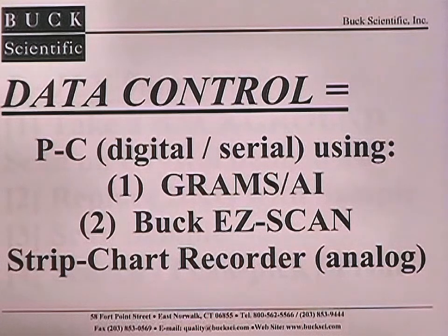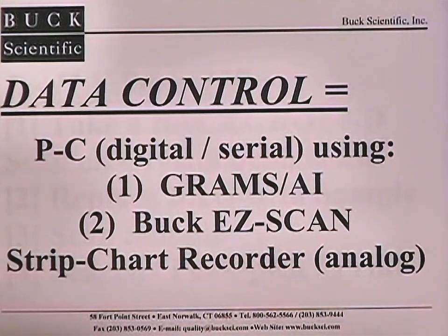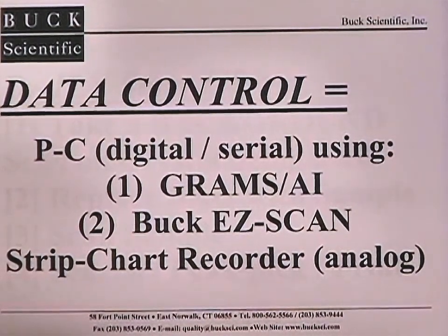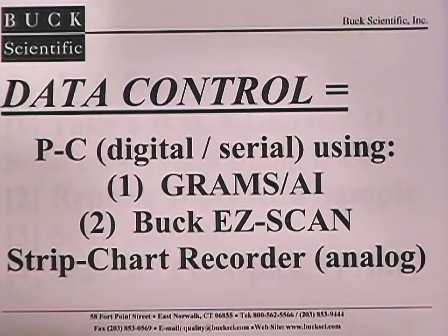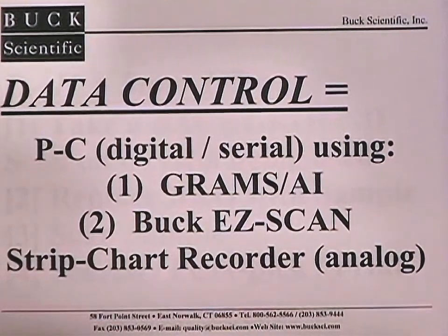Certain applications require an analog output, and the M500 has a 0 to 1 volt output that can go to a data logger or strip chart recorder. Let's take a look at the various connections at the back of the M500 to show where these components can be plugged in.